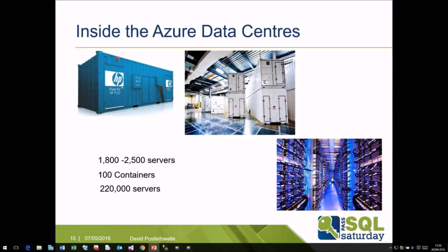In the data center, the servers are housed in standard 40-foot shipping containers. Each container holds anywhere between 1,800 and 2,500 servers. The shipping containers arrive fully built, so all the on-site engineers have to do is plug them in using a standard connector that provides power, cooling and network access. The servers remain inside their shipping containers inside the facilities, where they're placed side by side and stacked 2 high.